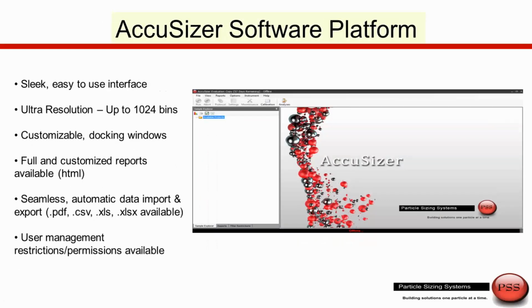The software platform that runs this system is our new AccuSizer software, which is relatively new, just introduced in the past year. It's a very improved, sleek, efficient system with up to 1,024 size channels, which is probably overkill for doing most contamination measurements. But it's very easy to use software. You can dock the maintenance or other parts of it, so you can operate just a portion of the software that is important to you for the task at hand. It's very nice for both importing and exporting data. Importing data, as I show, might be useful when we're setting up the tray for the auto sampler. And exporting is useful in order to take the data, create the ISO 4406 codes, and export it either in reports or electronically. There's also a lot of functions that help manage the permissions of who can actually run the system, make changes, etc.